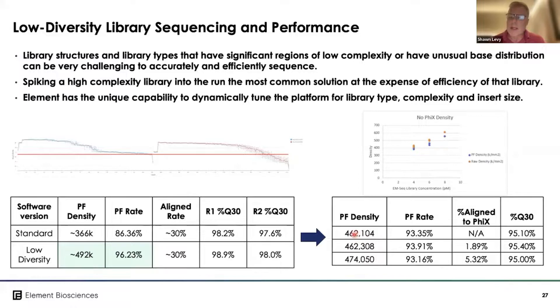This pass-filter density translates to between 900 million and 1 billion reads. We do see slightly higher sensitivity in low-diversity libraries when pushing to 1.2–1.3 billion reads, with a slight loss in pass-filter rate, which is why we're continuing to work on this. In summary, although the platform has been recently commercially launched, it is quite mature relative to the competition and ready for use under a variety of conditions. We support all major library preparations — there are 13 application notes and a large number of validated kits on the website.